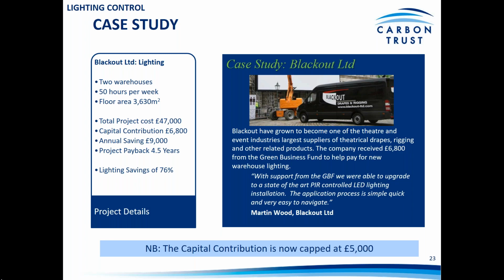So you can see here their project cost was in around £47,000. At that time, they were able to get a capital contribution of £6,800. That's now capped at £5,000. But in any case, they were able to see good savings of £9,000, and the project payback was 4.5 years, even without the contribution there. So you can see it's worth bringing controls in, and that would have provided a good proportion of the 76% lighting savings that they were able to achieve there.